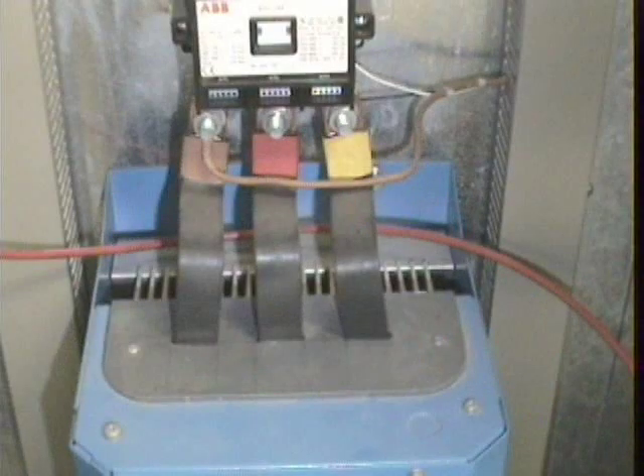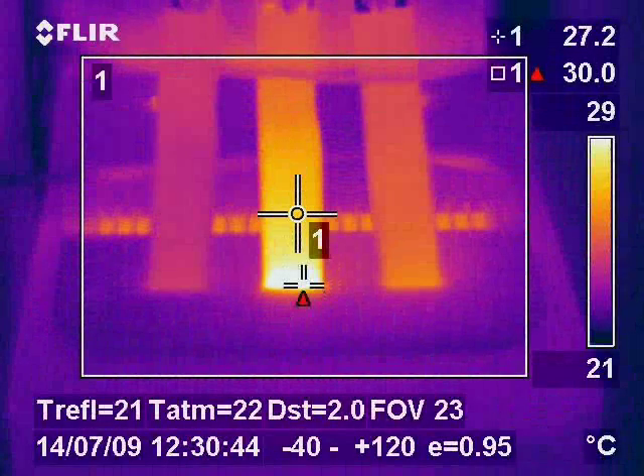Again in this image we see a VSD, this time a busbar connection to the incoming side of the VSD. The thermal image highlights a slight hot spot which may be the early stages of a potential fault on a busbar connection.